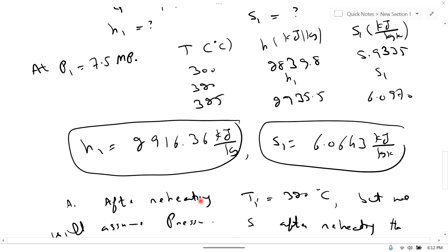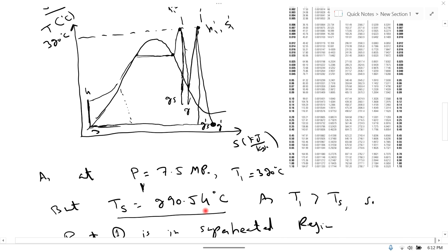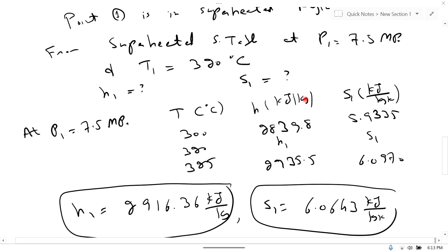It means that at inlet of the turbine temperature is 320 and at exit it is 207, but this difference is too small and 207 is too much temperature here.